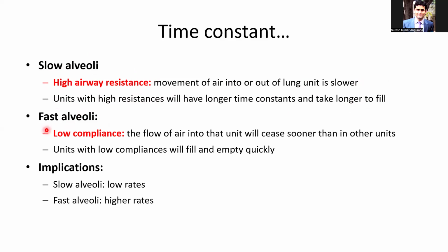Whereas in conditions with low compliance like pneumonia or ARDS, the flow of air into the unit will cease sooner than in other units.